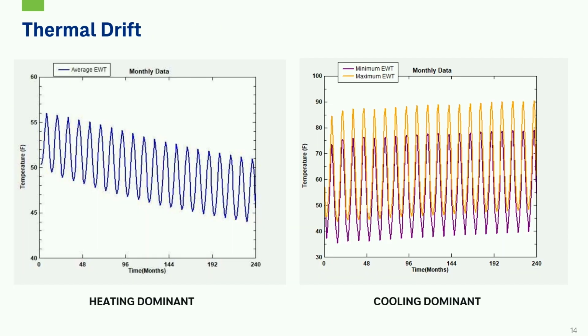So when you have those thermal imbalances, you're going to have a thermal drift in the ground. On the left, we can see for a heating dominant building, we have our average entering water temperature decreasing over 20 years, or you can see it's 240 months on the bottom. This is happening because we have more heating load in our building, so we're taking more heat from the ground than we're putting back into the ground in the cooling season.